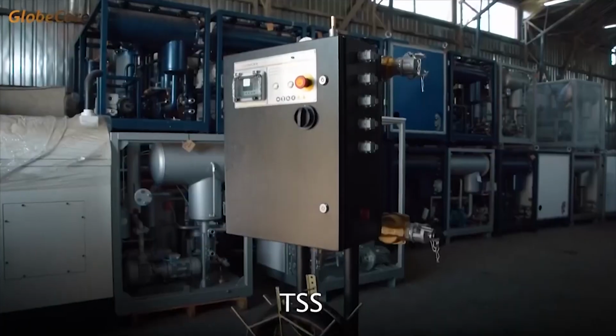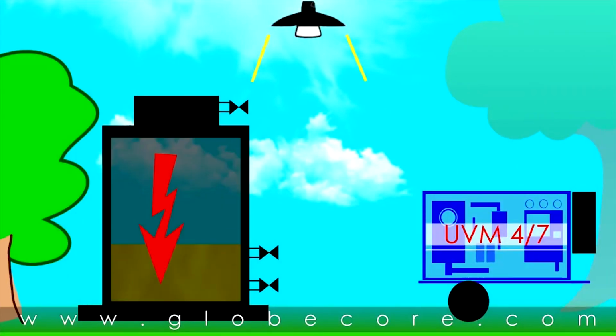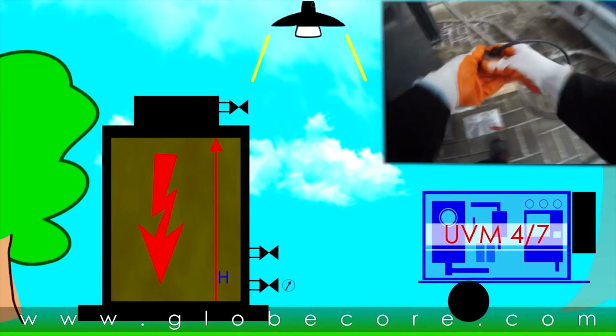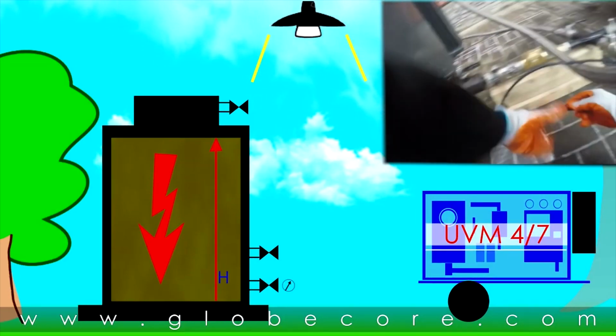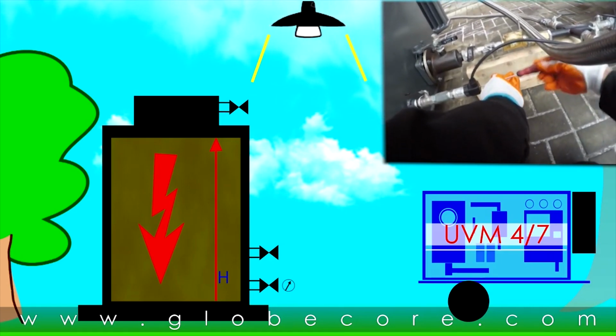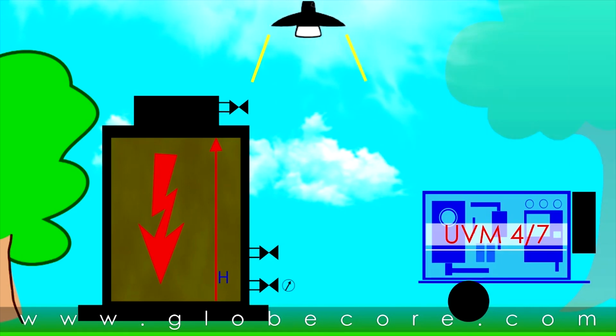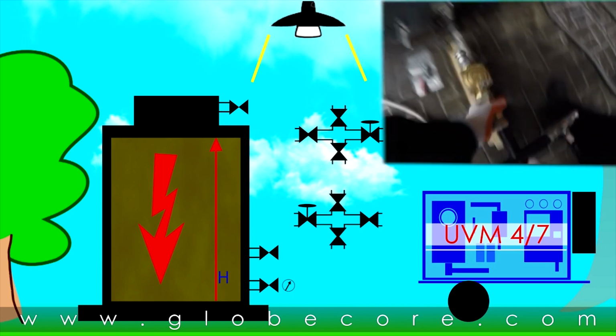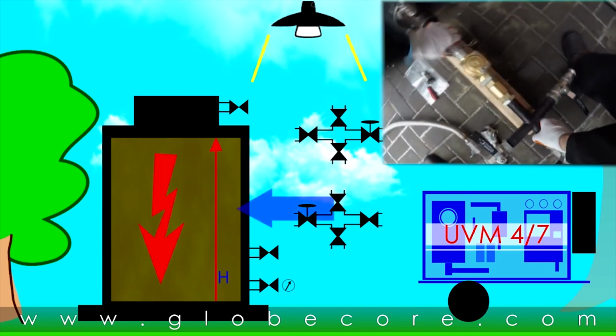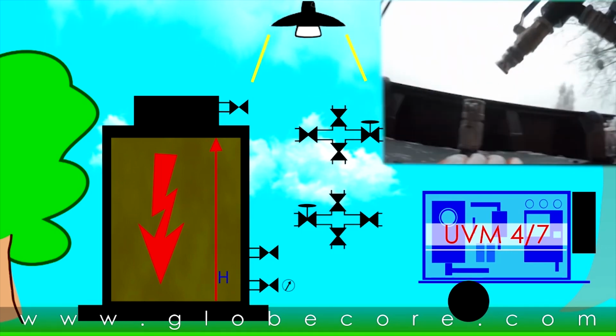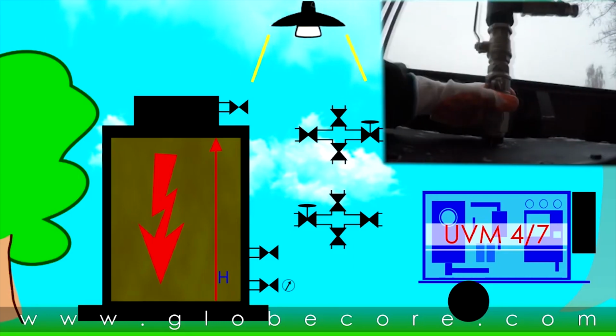The TSS transformer safety system is a standalone assembly controlling the level of oil in the transformer by a pressure sensor, which is installed in the transformer using transformer ports. The system is equipped with a control cabinet and valves, which allow to connect oil lines to the transformer and to process the oil so that no air is allowed into the transformer.